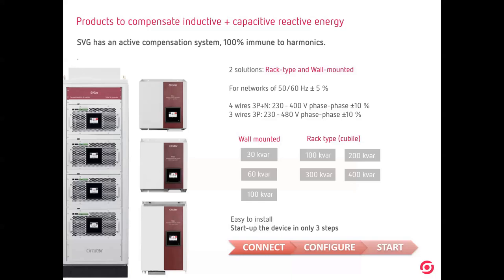So it's the same situation as the active filter, but now for compensating reactive power or energy, inductive or capacitive. You can set the cos phi that you want to reach inside the installation. It can be capacitive, it can be inductive, and this will inject power in order to reach this cos phi. If you are in capacitive, you will move to inductive. If you are in inductive, you will move to capacitive, in order to set cos phi one, or power factor one, or the one that you set.